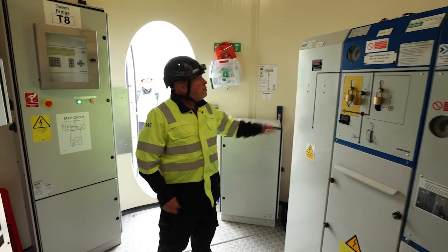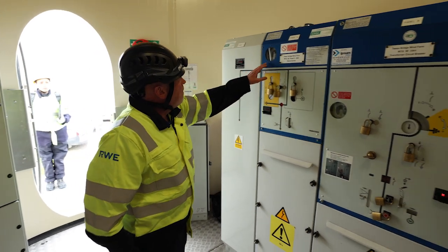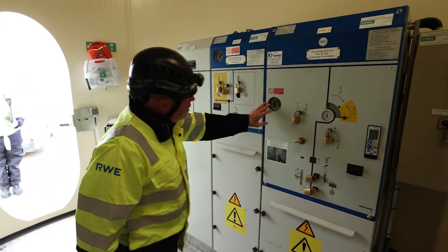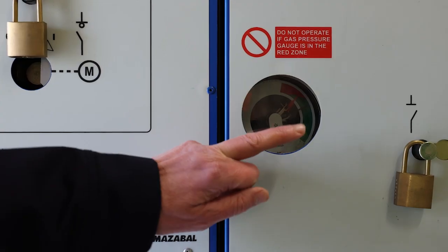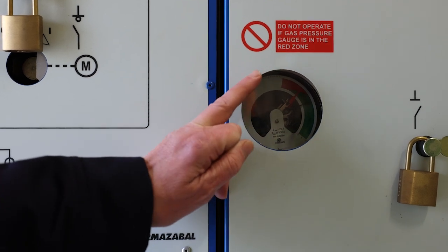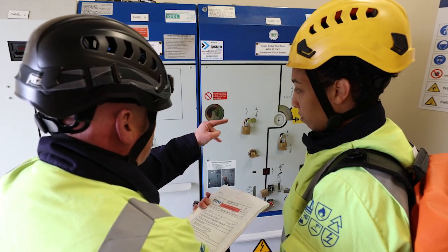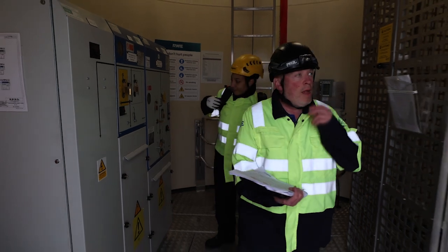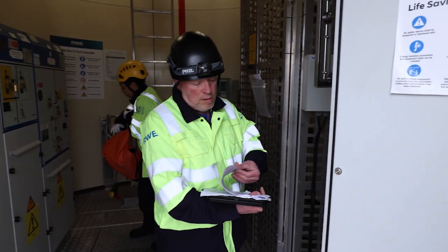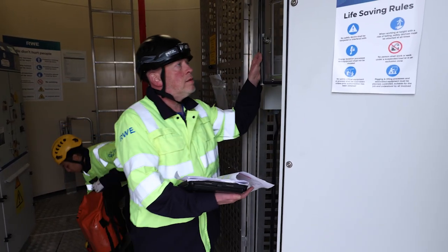We look for any alarms on the protection relay or any signs of deformity of the unit itself. If the switchgear has an SF6 gauge, we check that to make sure it is in the green. This indicates that it has the correct level of SF6 for the unit to operate safely. We'll keep checking what we can hear and smell while we're near the equipment. This is us actively maintaining a safe method of work, which is part of your general safety responsibilities. That's right. If we find any damage or cause for concern, we alert the control room and leave the turbine.